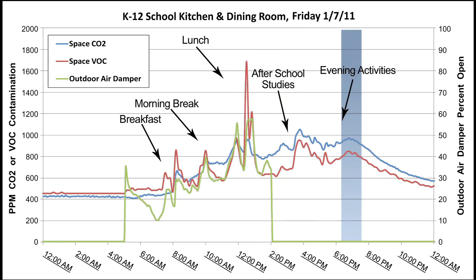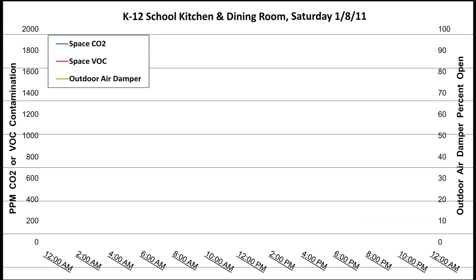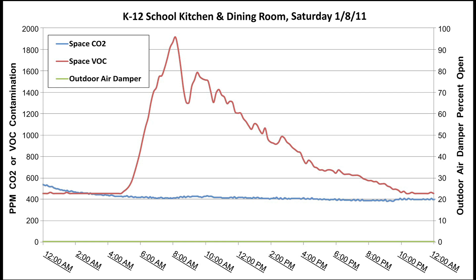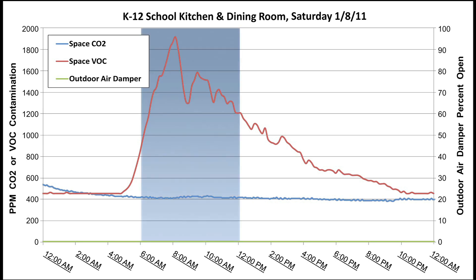There is an increase in VOCs from 6:15 p.m. to 7:30 p.m. due to student traffic in the area from an athletic event in another part of the school building. The space is considered unoccupied on Saturday, so the outdoor air damper is off. However, VOCs are being generated in the dining room from about 6 a.m. to noon due to a peewee wrestling tournament in the performance center across the hall. Wrestlers store their gym bags and other belongings in the dining area during the tournament, which accounts for the VOCs during that time. The CO2 sensor does not measure these VOCs, so you would not be able to ventilate away these VOCs and odors using the CO2 sensor.